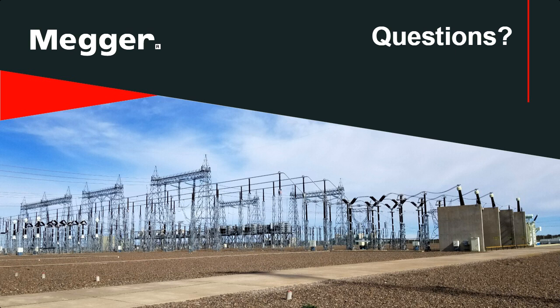So depending on whatever your maintenance protocol is, or if you follow IEEE or IEC. Most people only perform traveling measurements whenever they're doing like their 10 or 15 year PMs, right? So typically you should at least operate the breaker once every 2 years. So if you're just doing it to get a breaker operator signature every 2 years, and what that means is checking kind of how the coil and the motors, or the actual current that's going through those to operate those, you should do that about every 2 years. That way you can make sure that the breaker is free moving, right? And it's not going to be slowed down over time.